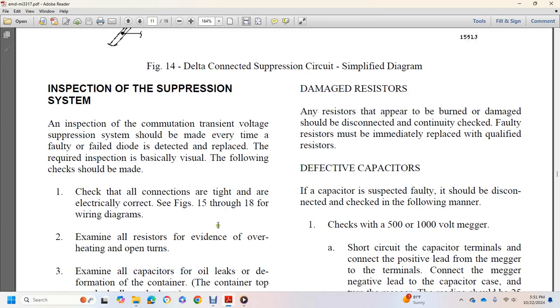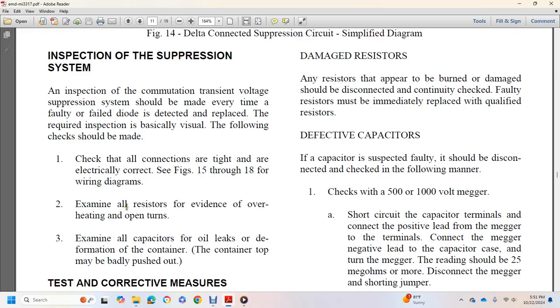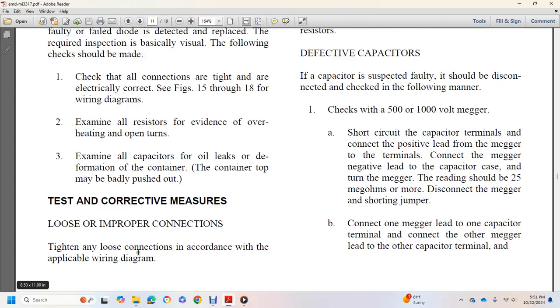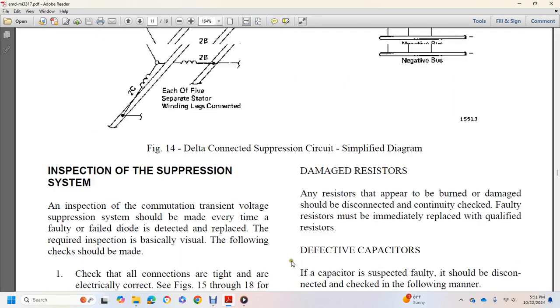Inspection of the suppression. Inspection of the commutation transient voltage suppression should be made every time a failed diode is detected and replaced. The required inspection is basically visual, with the following checks. Check that all the connections are electrically connected. See figures 13, 15 through 18 wire diagrams. Examine all the resistors for evidence of overheating or open turns. Examine all capacitors for oil leaks or deformation of the container top, which may be badly pushed out. Test and correct any loose or improper connection. Tighten any loose connection in accordance with the applicable wire diagram.